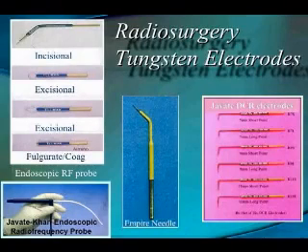There is also the extra fine Empire electrode, which is very useful in oculoplasty, which is narrow at its point but widens as it gets closer to the handle. The advantage of this design is that the micro-sharp tip concentrates the radiofrequency energy, resulting in minimal thermal damage to the adjacent tissue, which results in a thin skin incision with minimal scarring. The Javate DCR electrode design for endonasal DCR and standard external DCR. The Javate-Khan endoscopic forehead lift electrode, designed for endoscopic radiofrequency assisted forehead lift.